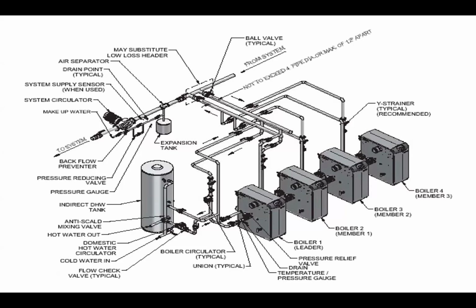Connected to a distribution system through primary, secondary T's, closely spaced T's, where we build a manifold, and then we have, in this case here, 4 boilers. Each boiler has its own pump by design from the manufacturer, because each boiler has its own circulator, its own pump, to provide the necessary flow through that particular boiler with pressure drop, et cetera. We just don't want these individual boiler pumps contending with, or being influenced by, say, a larger existing distribution pump.